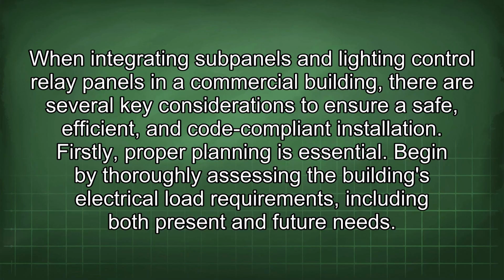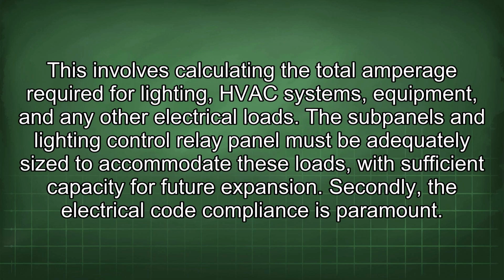When integrating subpanels and lighting control relay panels in a commercial building, there are several key considerations to ensure a safe, efficient, and code-compliant installation. Firstly, proper planning is essential. Begin by thoroughly assessing the building's electrical load requirements, including both present and future needs. This involves calculating the total amperage required for lighting, HVAC systems, equipment, and any other electrical load.